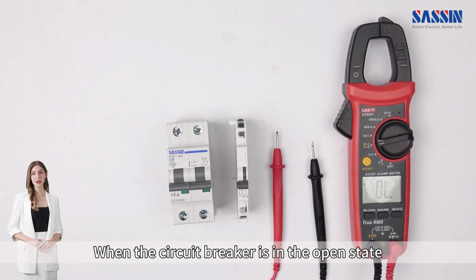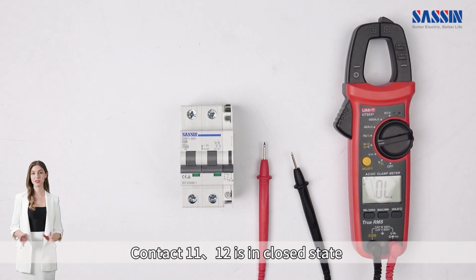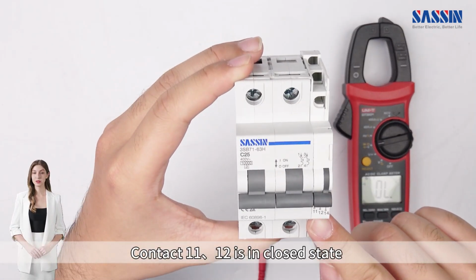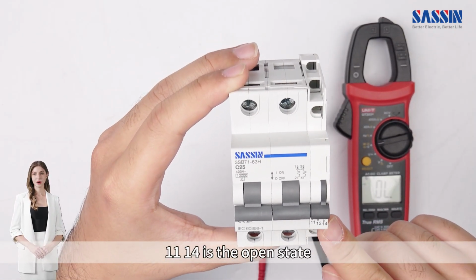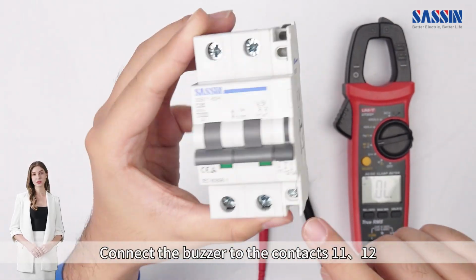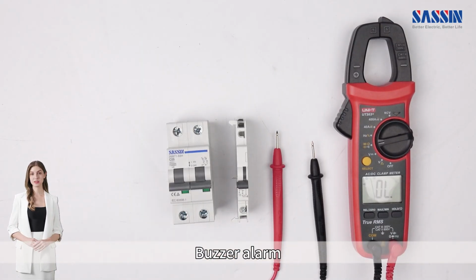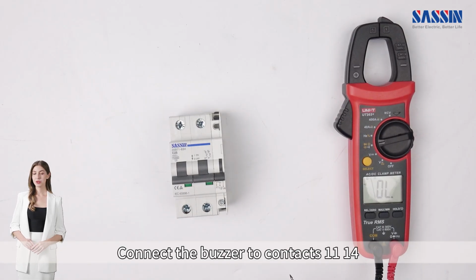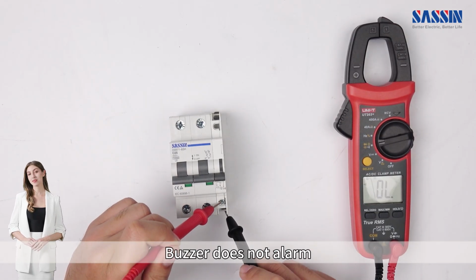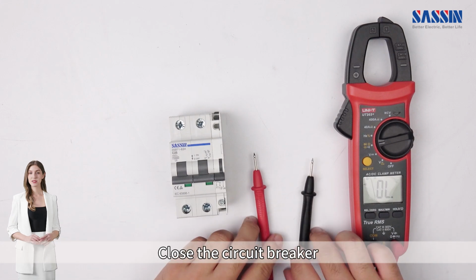When the circuit breaker is in the open state, contact 1112 is in closed state. 1114 is the open state. Connect the buzzer to the contacts 1112. Buzzer alarm. Connect the buzzer to contacts 1114. Buzzer does not alarm. Close the circuit breaker.